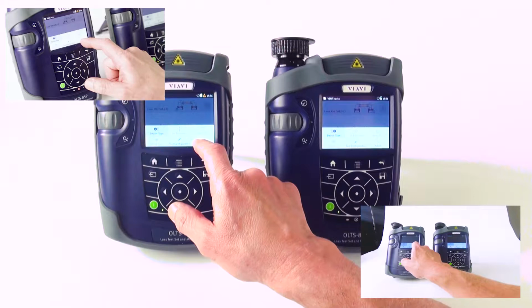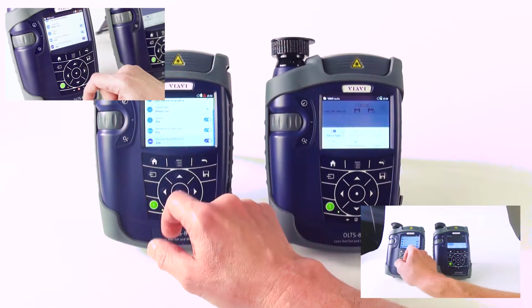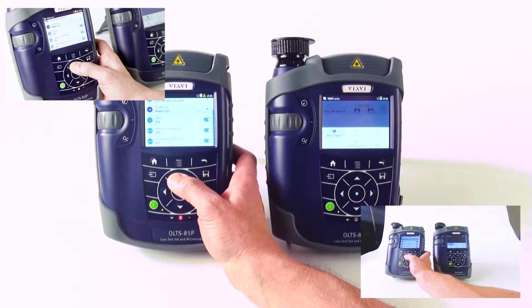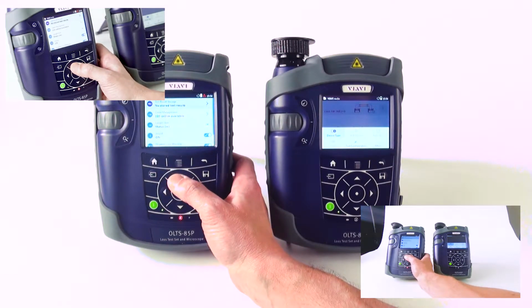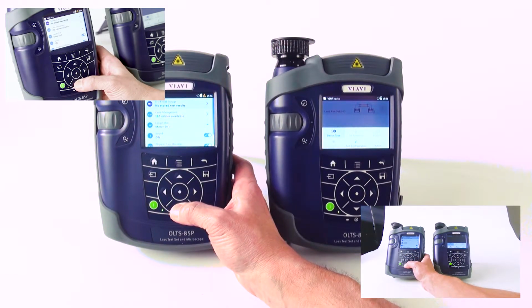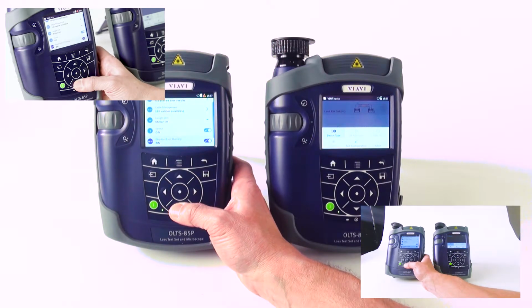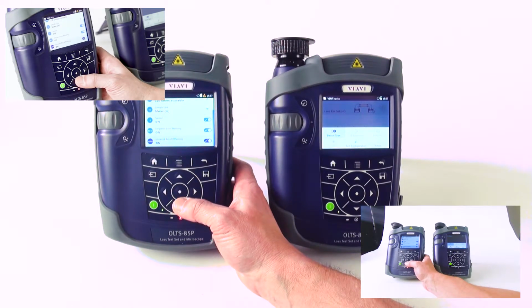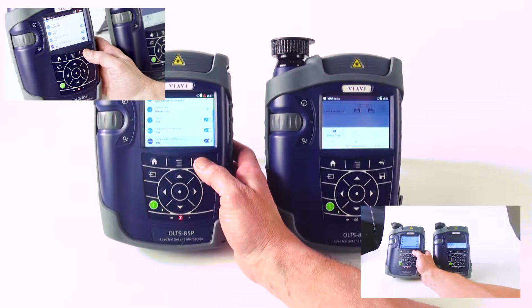Within the loss length application, on the local unit, we also have a more button, and it gives you some different options: you can look at your stored test results, your cable database, whether you want to be in feet or meters, whether the sound is on or off (you'll hear beeping as we connect things together in later videos), the negative loss warning, which I like to have on, and the unsaved result warning, which prevents you from exiting screens without having saved the results. I like to leave all those 3 things on.